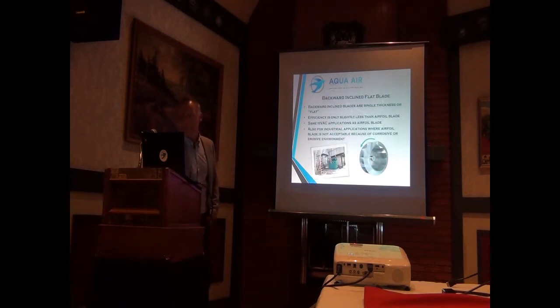Backward inclined flat blade was one of the first inventions or engineering improvements for efficiency on blades. Backward inclined blades are single thickness and flat. They curve away from the airfoil as it rotates in the direction of airflow. Efficiency is only slightly less than the airfoil blade fan. The airfoil blade fan, which we'll talk about in the next slide, has a rounded edge. This is just the flat blade. These push on the air, often used in pressure fan applications.